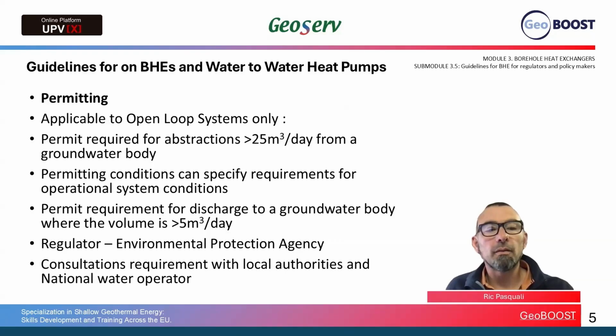There are also permits required for discharge of groundwater to a groundwater body. In terms of the re-injection of a water-to-water heat pump system, those permits are required where volume exceeds 5 cubic meters per day. The regulator is the Environmental Protection Agency, and there is a dedicated application process for these permits that are to be submitted to them.